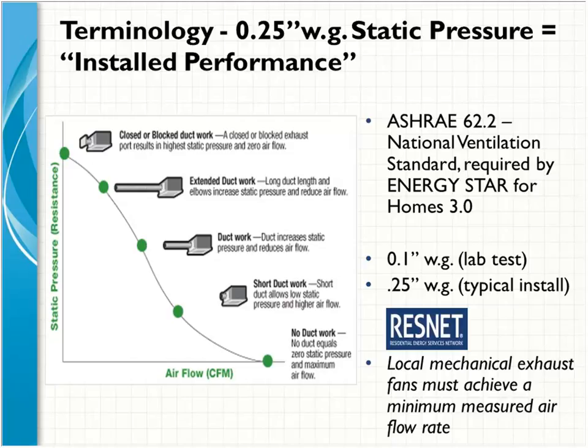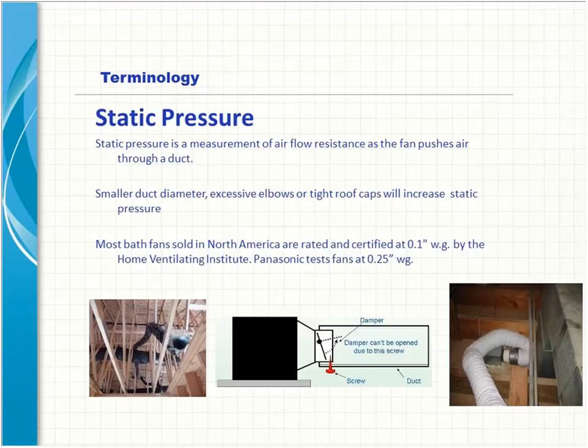And the answer is usually no, because that would be about 8 feet of straight pipe, 1 elbow, and then out through the termination. And it's very unrealistic that in today's homes, with bathrooms located in the middle of the floor plan, you can get out to the exterior of the building with just 0.1 inches of water gauge in terms of ductwork. So we feel that 0.25 is a better number to test at. The fans should be tested, we feel, at a higher water gauge. 0.25 is more realistic for a residential install. So we test all of our products at that and publish that information on all of our products. I don't want to get too much into product, but just wanted to mention that 0.25 is a better representation of what fans are actually installed with in terms of static pressure.